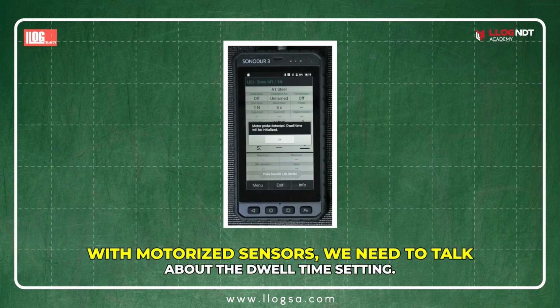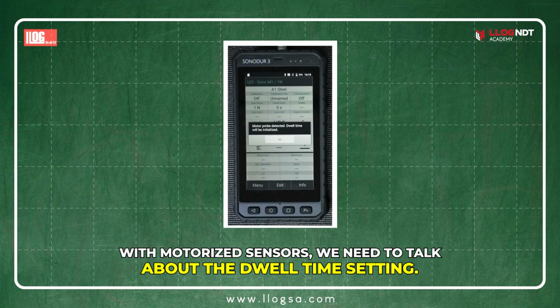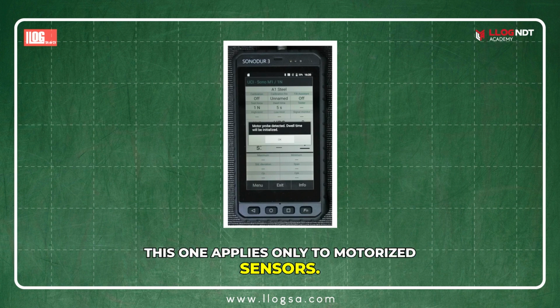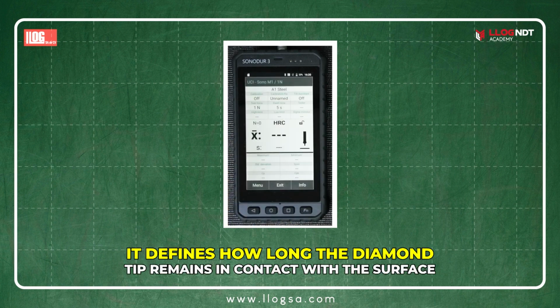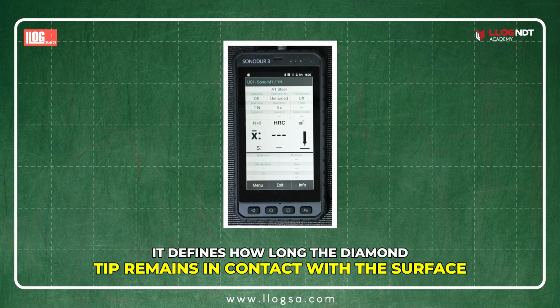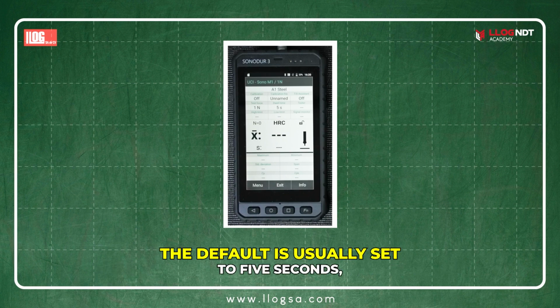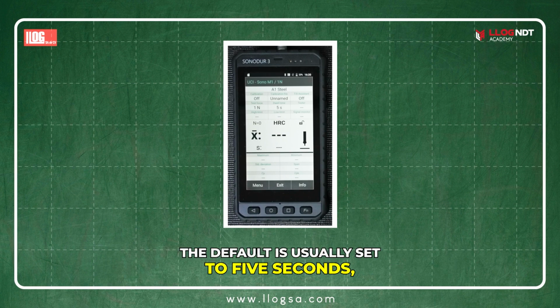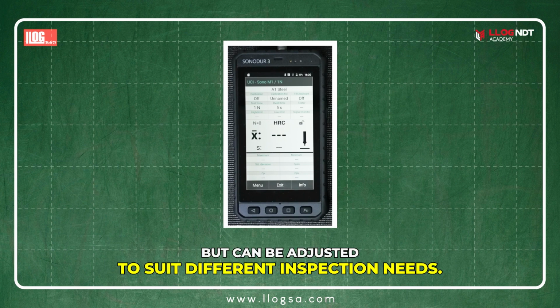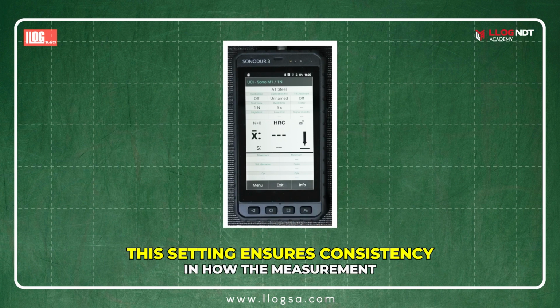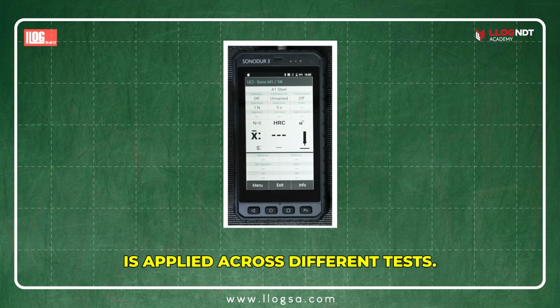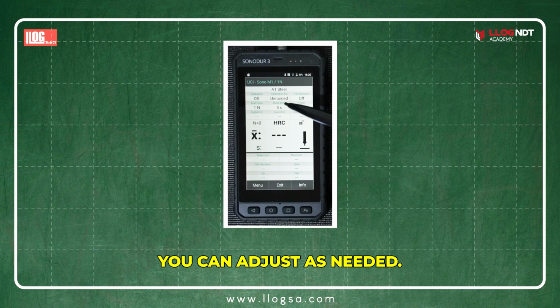With motorized sensors, we need to talk about the dwell time setting. This one applies only to motorized sensors. It defines how long the diamond tip remains in contact with the surface under load. The default is usually set to 5 seconds, but can be adjusted to suit different inspection needs. This setting ensures consistency in how the measurement is applied across different tests. You can adjust as needed.